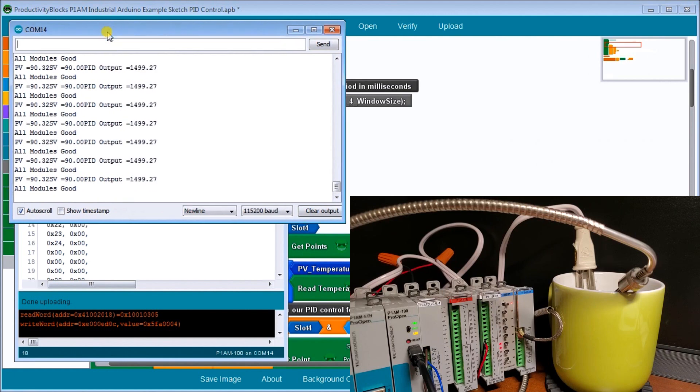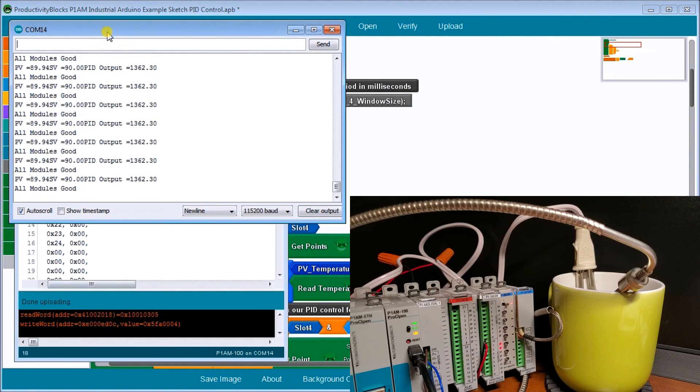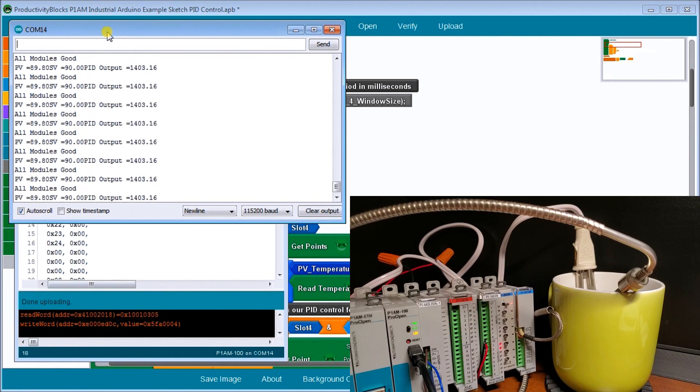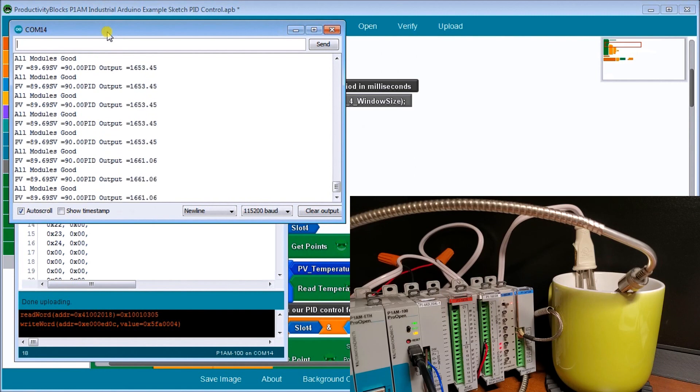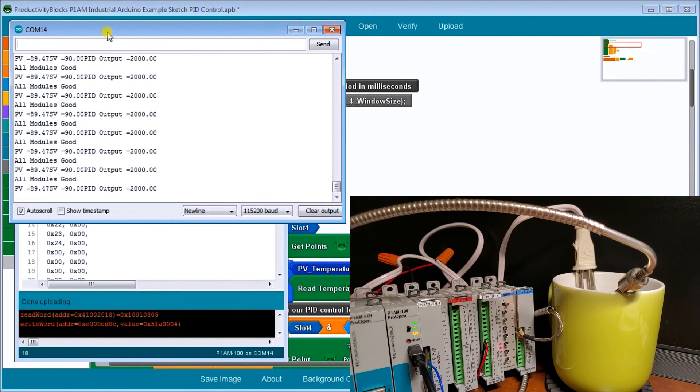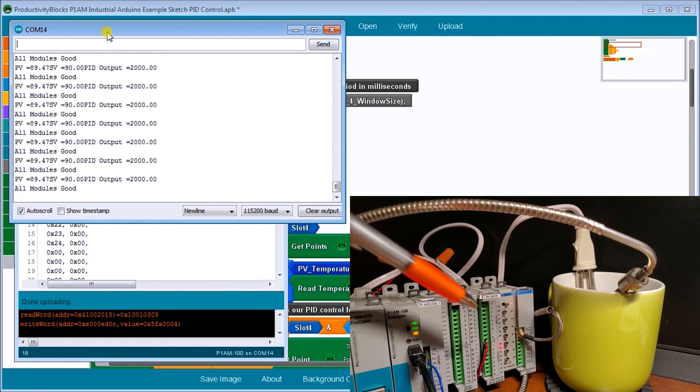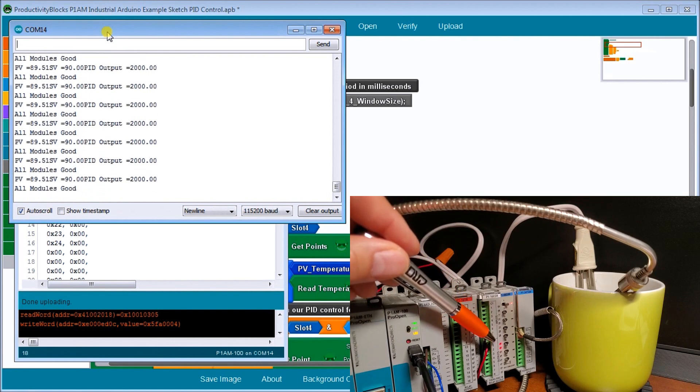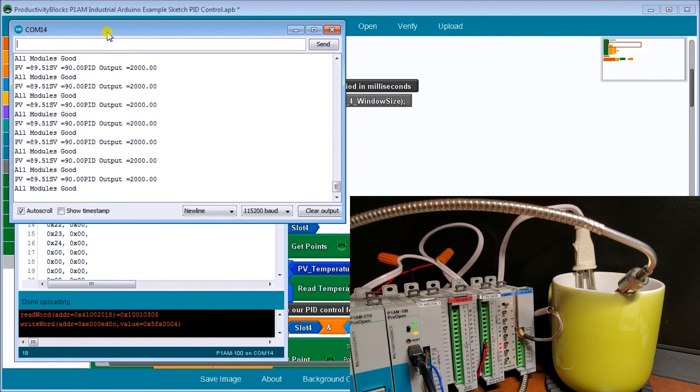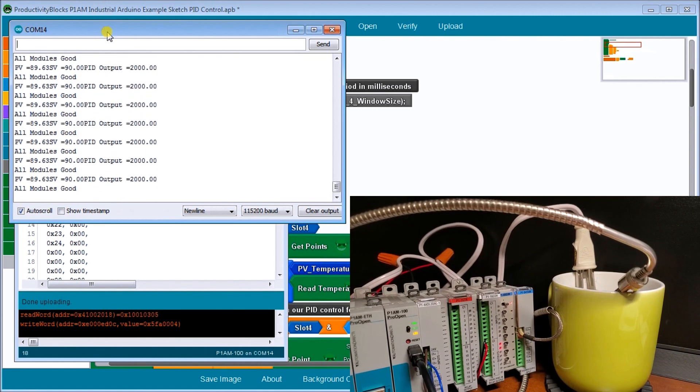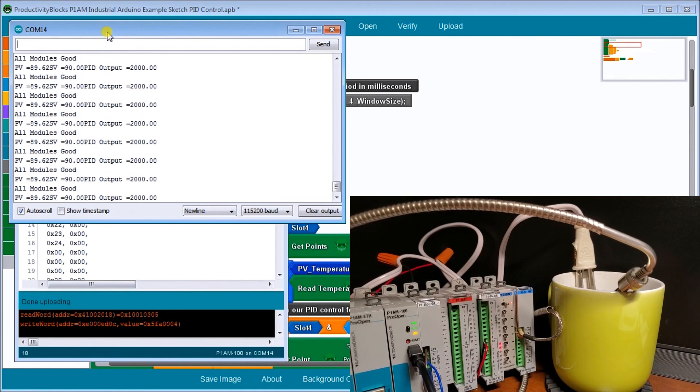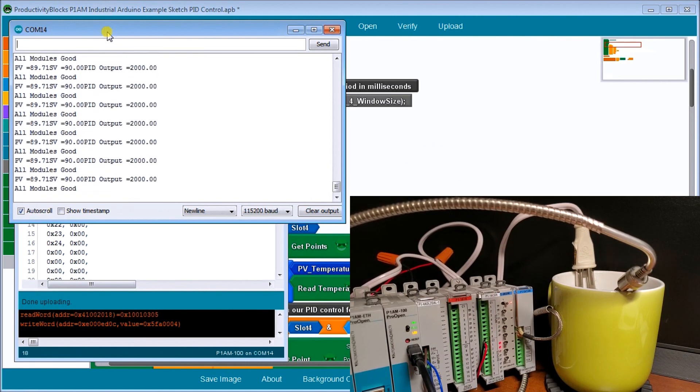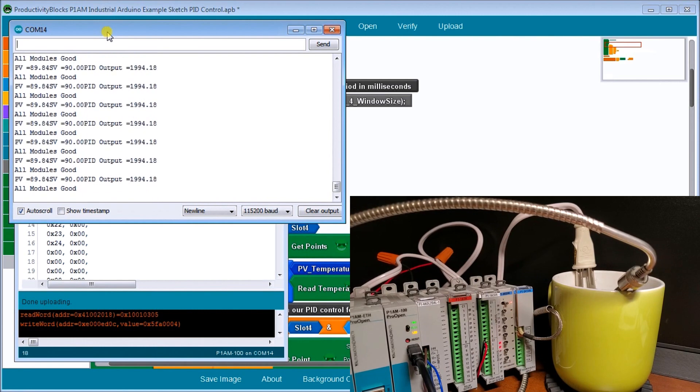And here is our PID loop running right now. You can see our temperature is being controlled between 89.7 and 90.5. So my relay is actually controlling right here. And it's turning on and off that heater based on that relay condition. And you can see the output. And as the output goes closer to the 90, then that output range starts dropping off. Showing indication less and less of our heater is required.